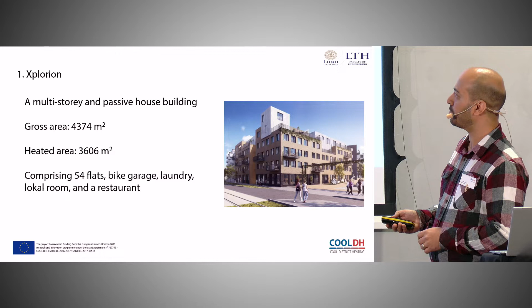In fact, Xplorion is connected to a low temperature network, but there is an additional booster heat pump with a heat exchanger to simulate an ultra-low temperature demo. As you can see in this picture, the heat exchanger at the top reduces the temperature from, for example, 60 to 45 to input the heat pump, and the heat pump will increase it again to 60 degrees to provide both space heating and domestic hot water for the flats.